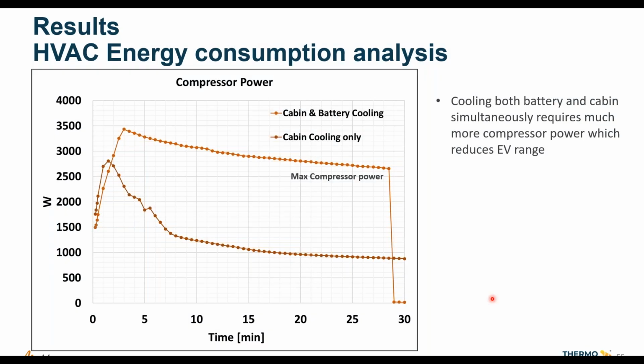So when we look at the compressor power, the orange one shows when we cool both cabin and the battery, where you see that the compressor power still remains on the higher side, since the battery cooling requires much more power, and that's why you see a very big difference here. And when you just look at the cabin cooling only without battery, it is much lower. So this shows that cooling both cabin and the battery requires more power.